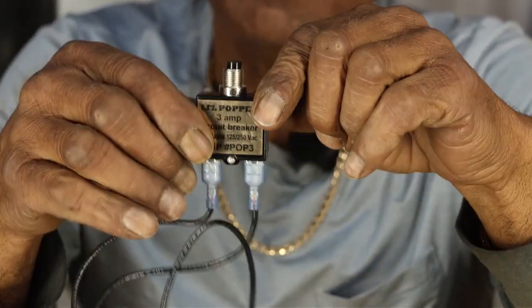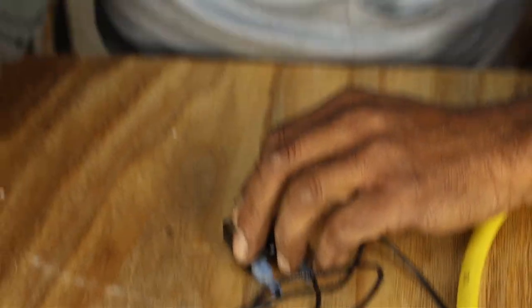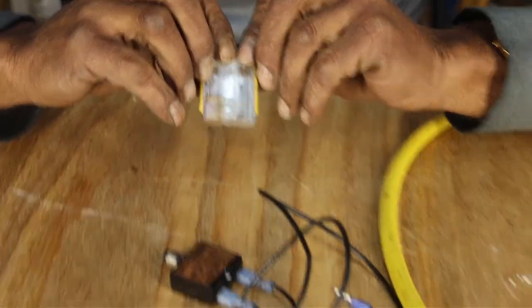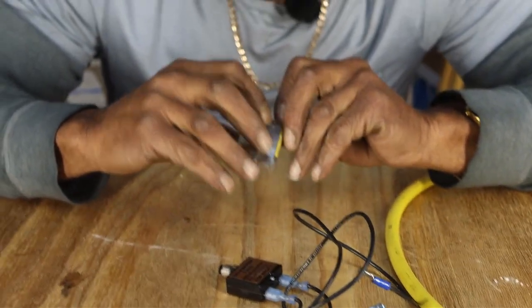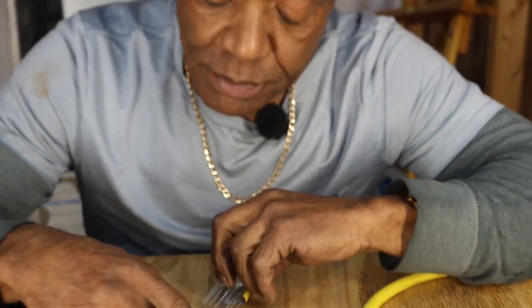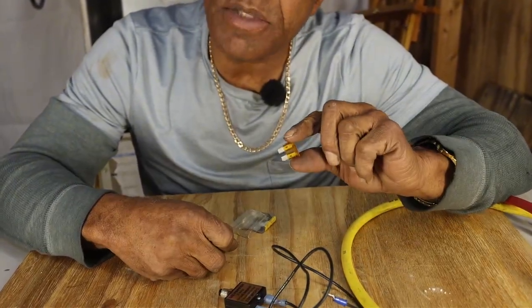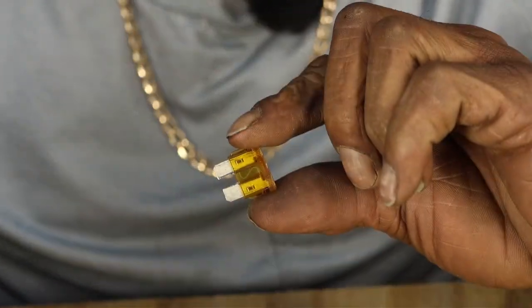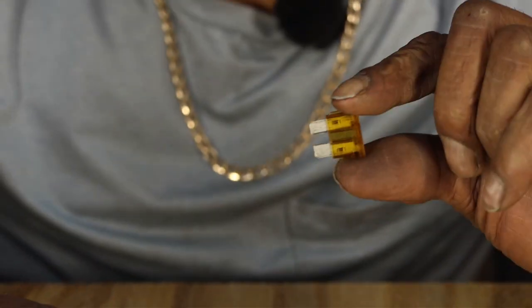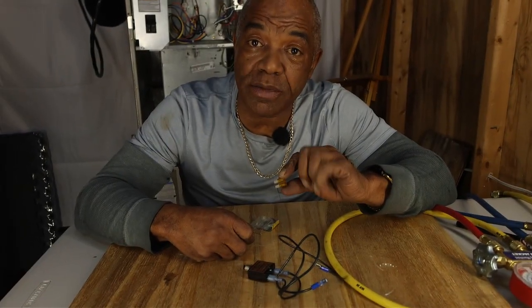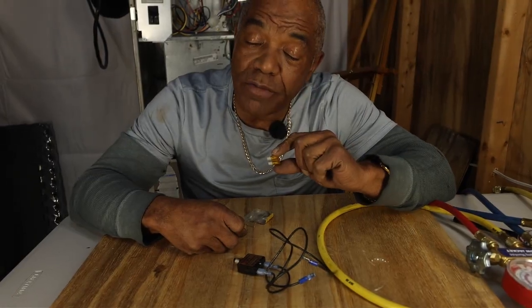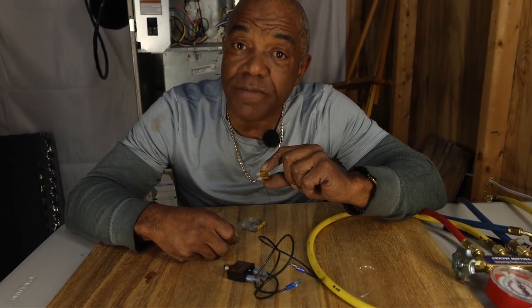has saved me so much time and also saved me so many of these 3 amp fuses. Well, not every unit, 98% of every unit we work on has one of these fuses on the circuit board. And sometimes that's the whole problem. I've gone to so many homes where this fuse was bad. I replaced the fuse and the system's working wonderful. I charged the people $105 for a service call because I came out and I charged them $6 for the fuse. My total invoice was $111. I was in their house for 15 minutes.